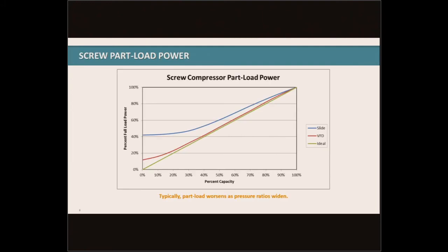Here's a chart showing the difference in efficiency among different types of capacity control. Most screw compressors operating with a slide valve — a pretty standard method — show their percent full load power trending like a hockey stick as capacity decreases toward about 40%. The VFD, by contrast, pretty closely hugs the ideal line down to lower capacities. For example, at 20% capacity, a compressor with a slide valve uses about 42% of its full load power while only delivering 20% capacity. With a VFD at that same point, you're at 20% capacity and about 22% power — roughly half the power to get the same capacity.